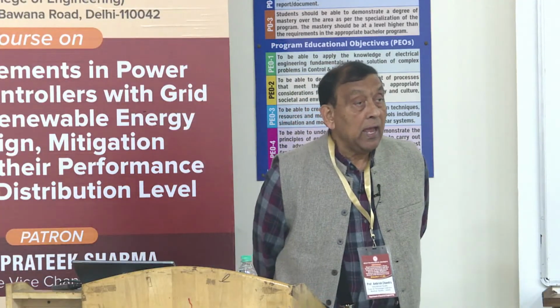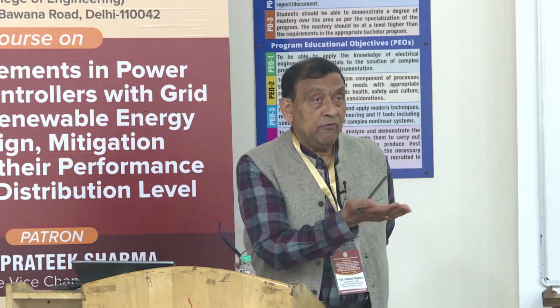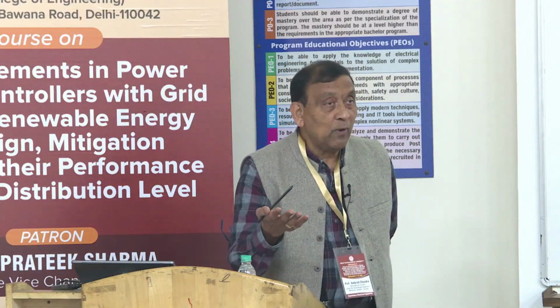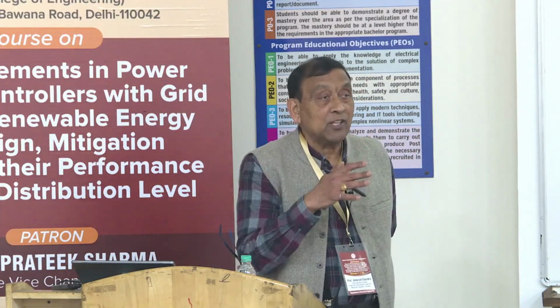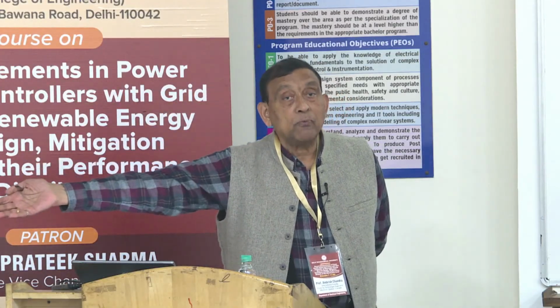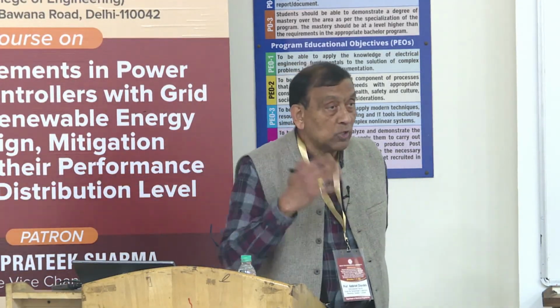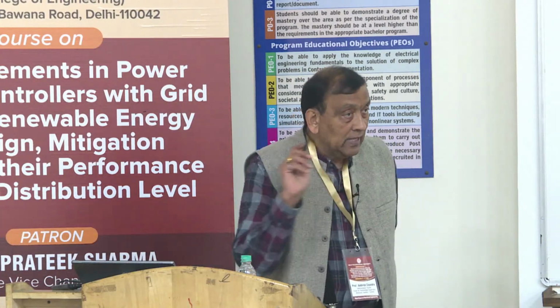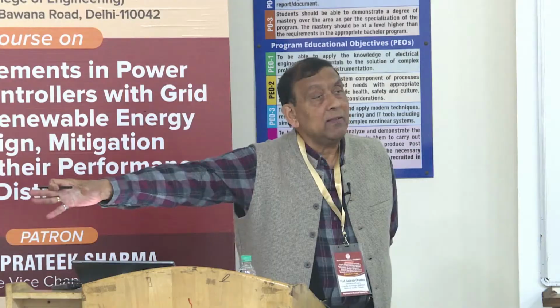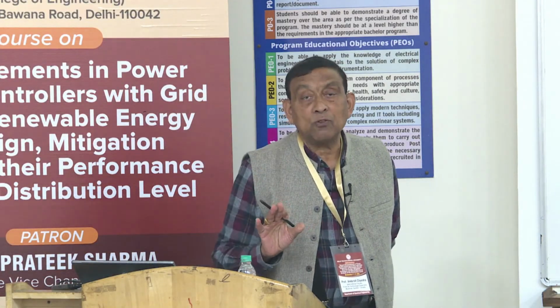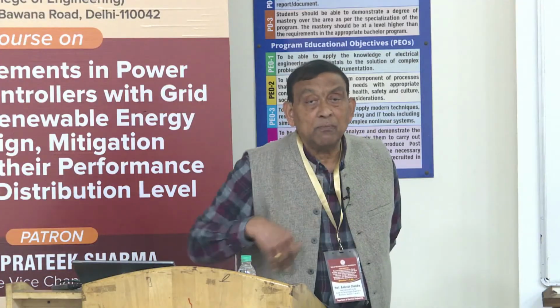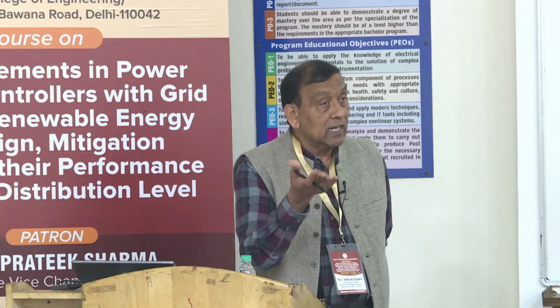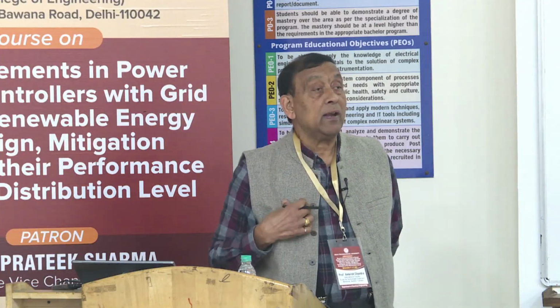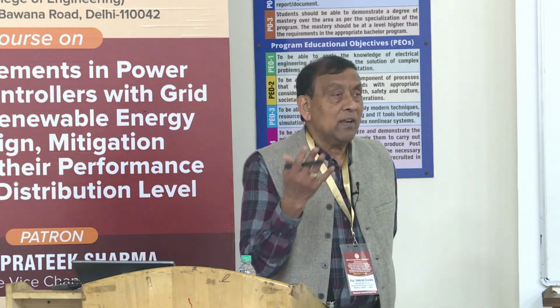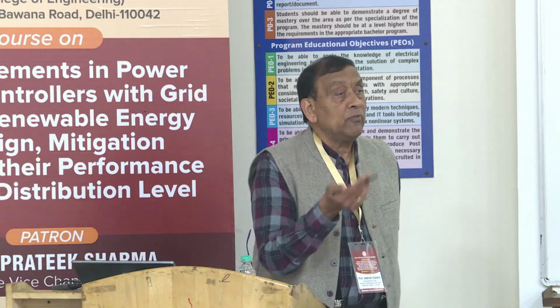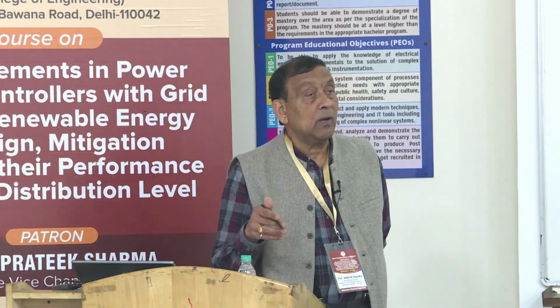3-phase transformer. And then what if you want an emergency transformer? If you have one big 3-phase transformer, does it mean you need another such big 3-phase transformer, which will cost a lot? But if you have 3 single phase transformers, then you need only another small single phase transformer to replace one if there is some repair. Moreover, it is easy to repair a single phase transformer. It is very difficult to repair a 3-phase transformer. So these are some advantages and disadvantages of a 3-phase transformer or single phase transformer, right?